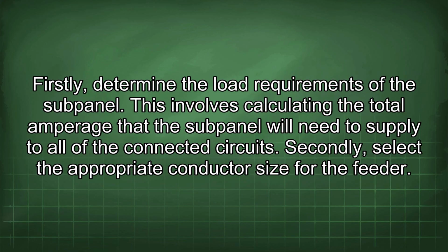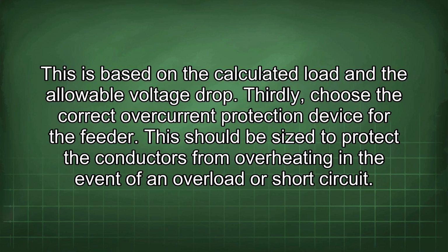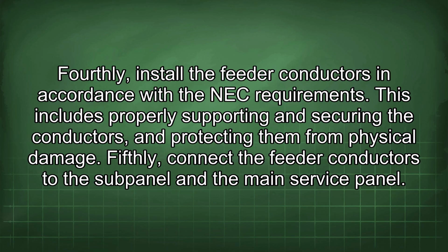Firstly, determine the load requirements of the subpanel. This involves calculating the total amperage that the subpanel will need to supply to all of the connected circuits. Secondly, select the appropriate conductor size for the feeder. This is based on the calculated load and the allowable voltage drop. Thirdly, choose the correct overcurrent protection device for the feeder. This should be sized to protect the conductors from overheating in the event of an overload or short circuit. Fourthly, install the feeder conductors in accordance with the NEC requirements. This includes properly supporting and securing the conductors and protecting them from physical damage.